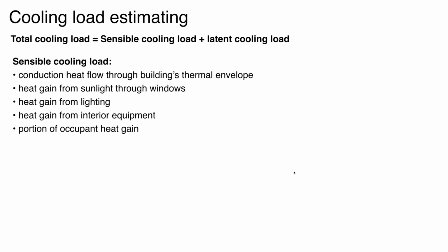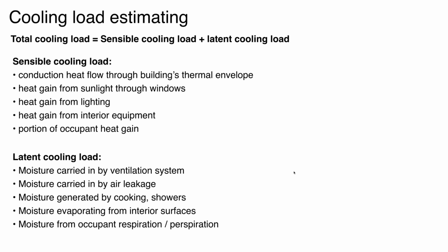You have sunlight through windows. If you have lights or other interior equipment, computers or anything like that running, all the wattage going into that interior equipment ultimately becomes sensible heat gain to the space. And a portion of the metabolic heat output of occupants also contributes to the sensible cooling load. Latent cooling load is associated with anything that adds moisture to the air. So it could be moisture carried in by ventilation air, or moisture carried in by air that leaks into the building envelope. Certainly in residential, you're cooking, you're taking showers, maybe you're washing the floors, anything like that. That moisture evaporates, and that becomes part of the latent cooling load. And then occupants, respiration, perspiration, that contributes moisture into the space too.